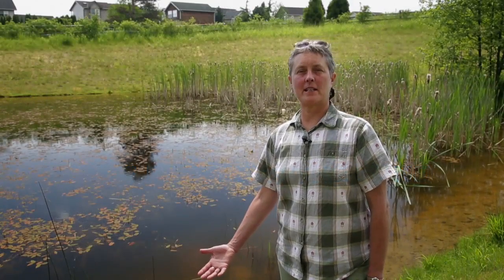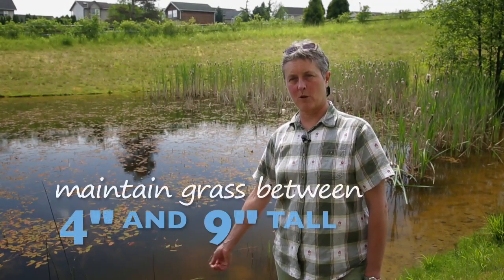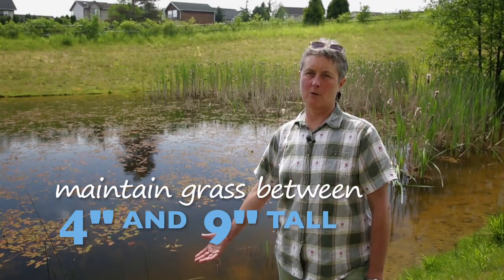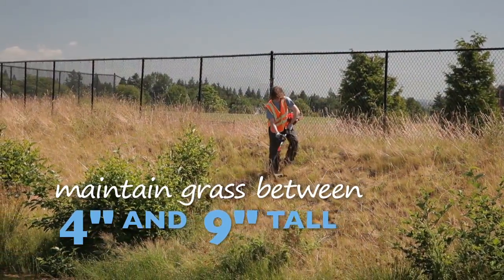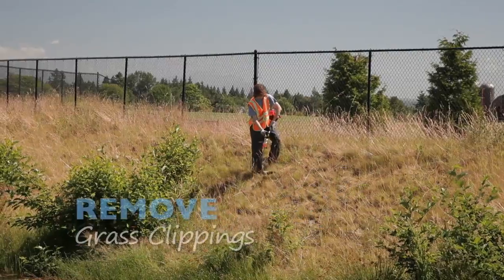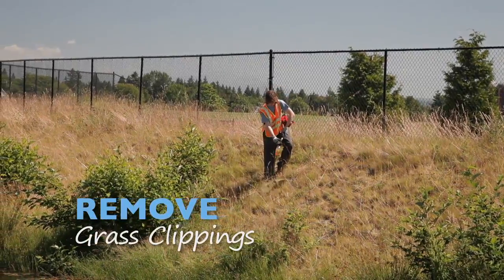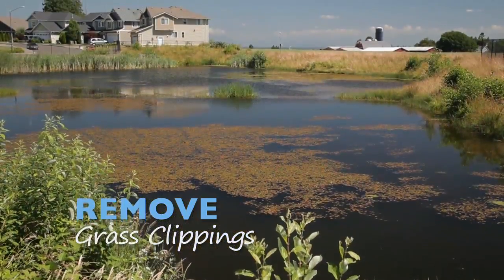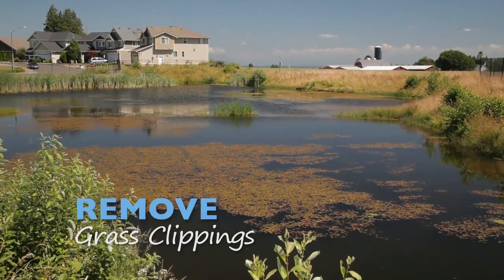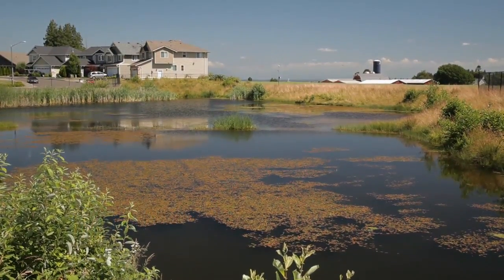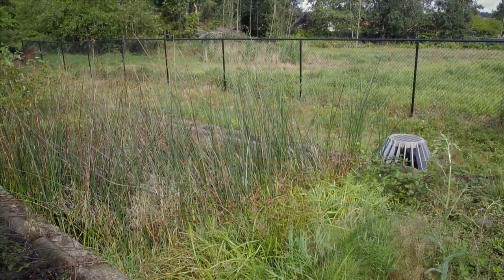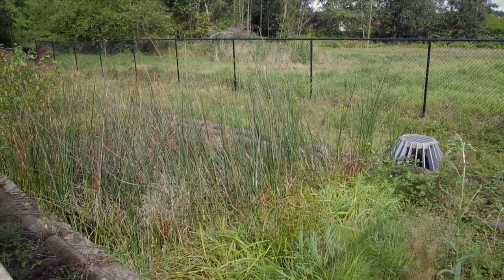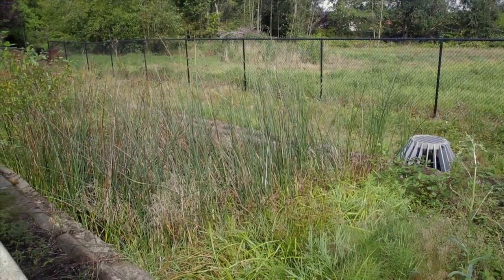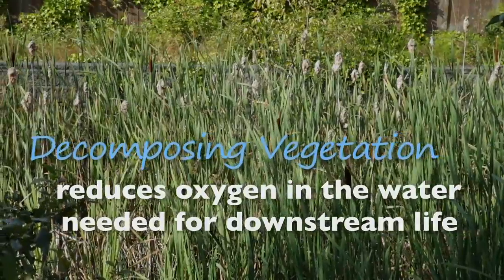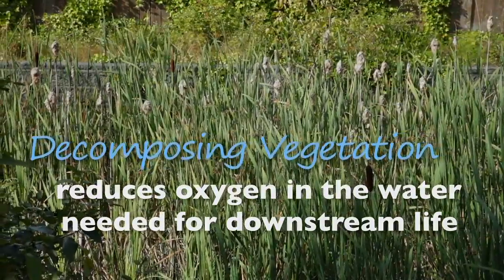It's pretty easy to maintain the grass. You want to keep it between 4 and 9 inches tall, and you can use a lawnmower or a weed eater and just regularly mow the side walls of the pond, and then the grass should be removed from the stormwater pond because we don't want the grass to get into the water. If cut vegetation is left in the pond, it can reduce the water storage capacity of the pond. Also, as the grass clippings decompose, they can rob the water of oxygen needed for a healthy downstream ecosystem.